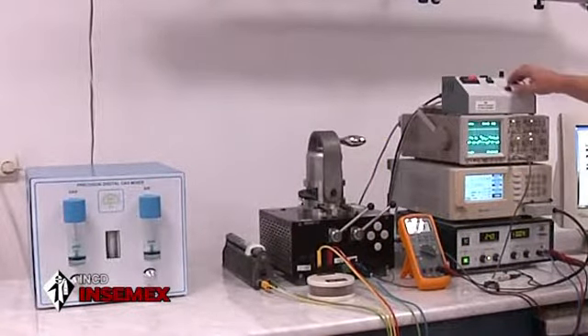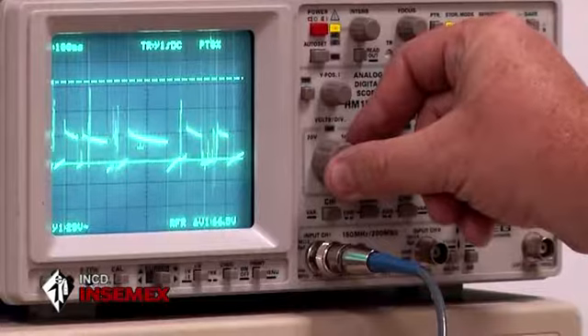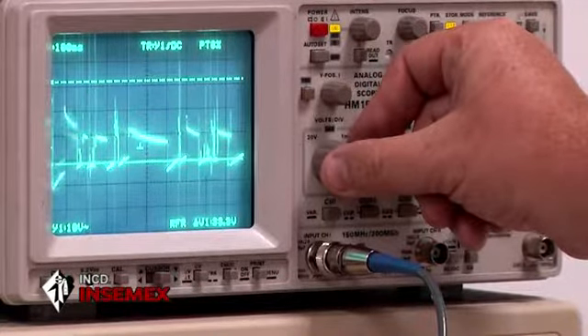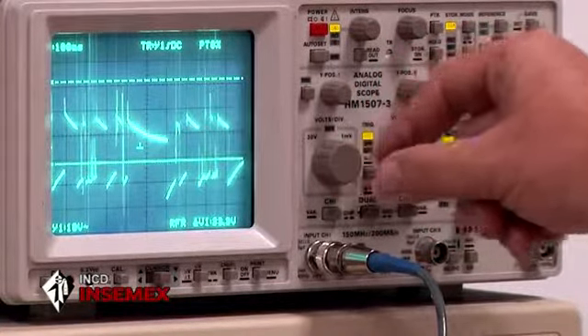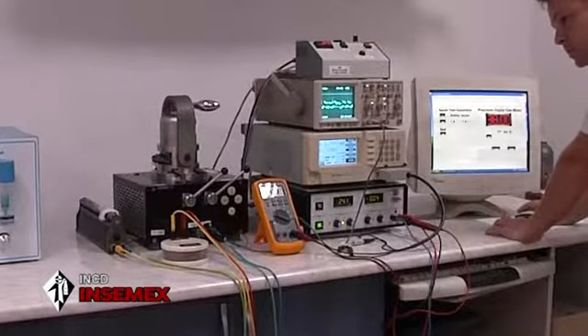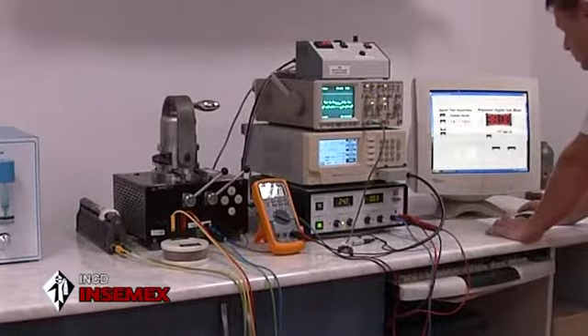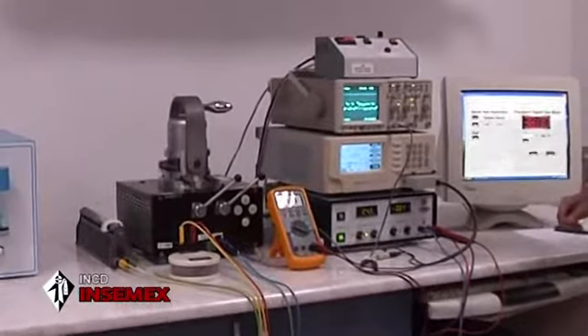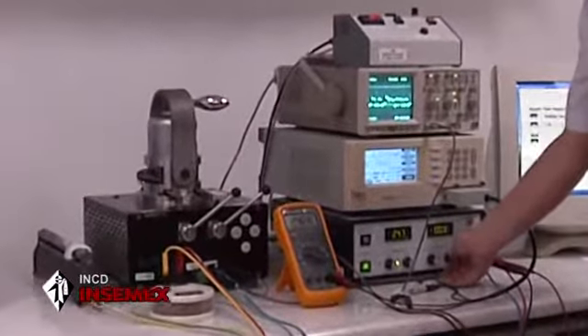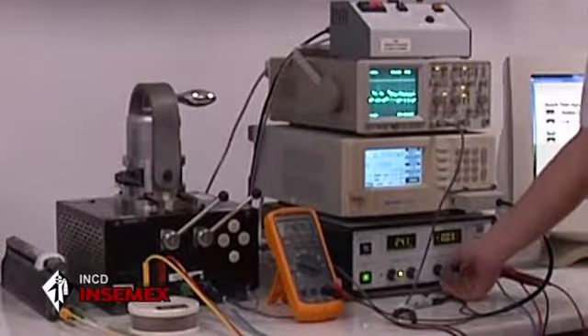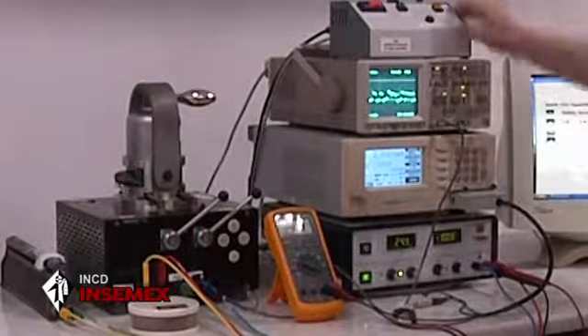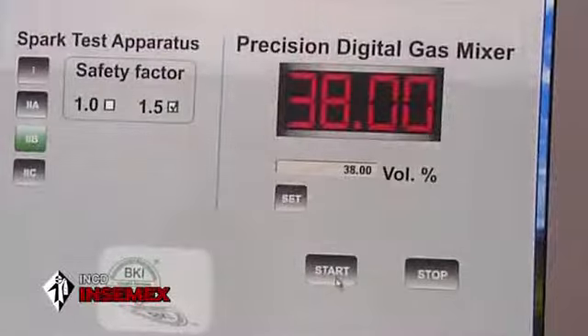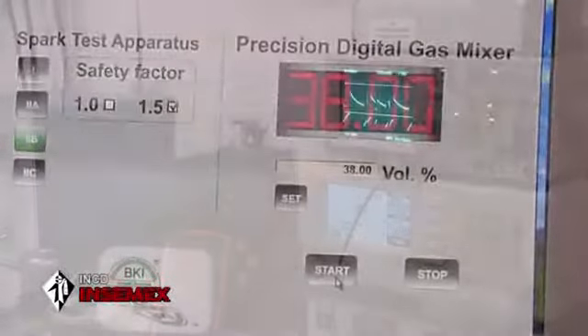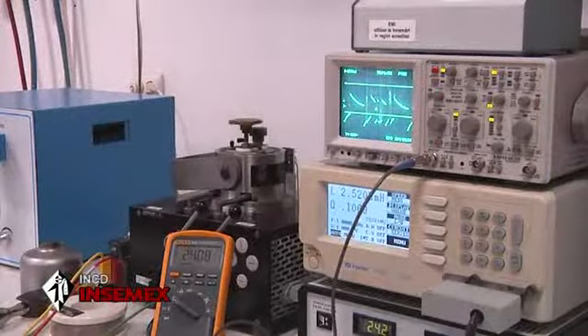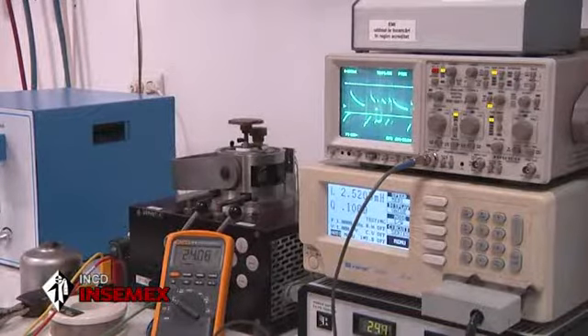In operation, there are generated sparks inside the testing chamber where the explosive mixture is located, mixture consisting in air and flammable gases, such as methane, propane, ethylene and hydrogen. If the sparks generated by the energy provided by the tested equipment do not ignite the explosive test mixture, then the equipment passed the non-ignition test. The sensitivity of the test stand is verified through the calibration process, in which the test mixture has to ignite from the sparks generated by a supply source which has imposed electrical parameters.